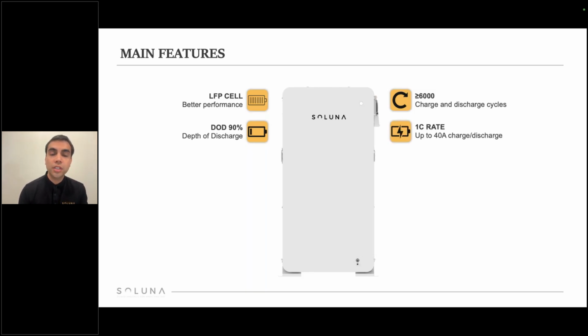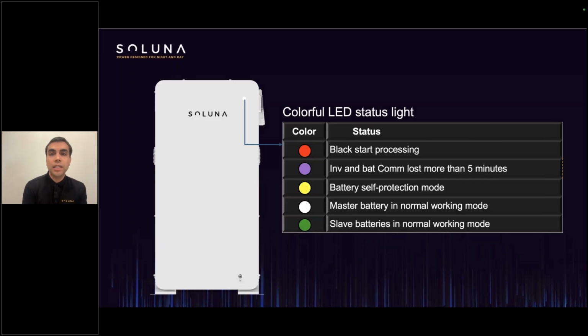The depth of discharge is also 90%. It's 1C rated for 40 amps, and it has the colorful LED status light with the red button. The red light will be representing the black start, and the inverter and battery communication lost for more than 5 minutes in communication will be represented by purple light. The yellow light will be showing battery self-protection mode. The white light will be the master battery, and the green light will be the slave battery.